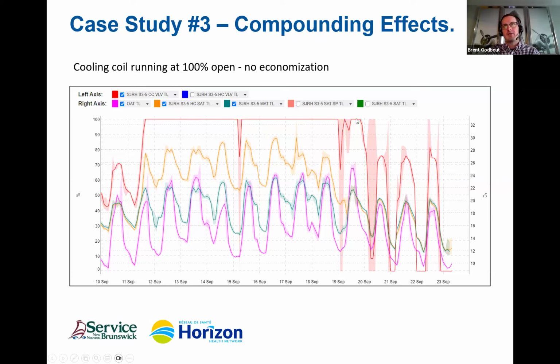Then you can see after we fixed it, it dropped down. But if you notice here at nighttime, we actually were totally shutting that valve off. So the cooling coil valve is now completely shutting off. And that's because we have economization or free cooling at this hospital.